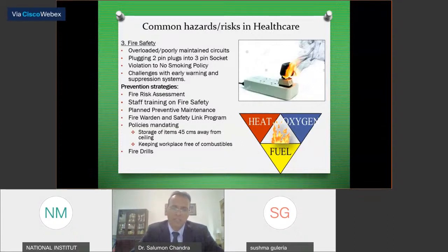You will also have policies mandating storage of items at least 45 centimeters away from the ceiling - no item should be piled up to hit the roof. This is because your sprinkler system won't be effective if items are too close to the ceiling. You may have a sprinkler system in some areas and not others, but it's always good to be consistent.